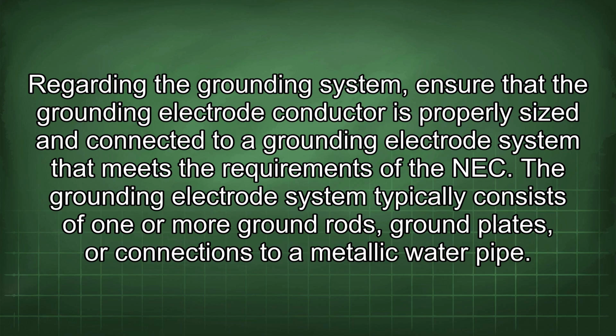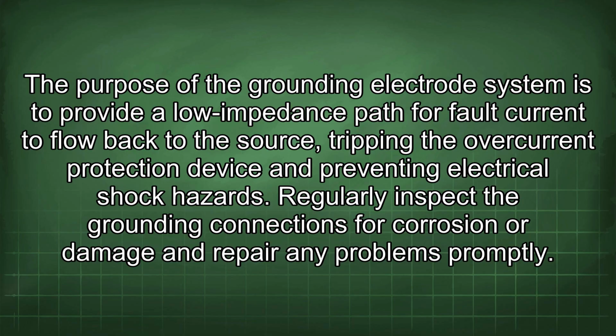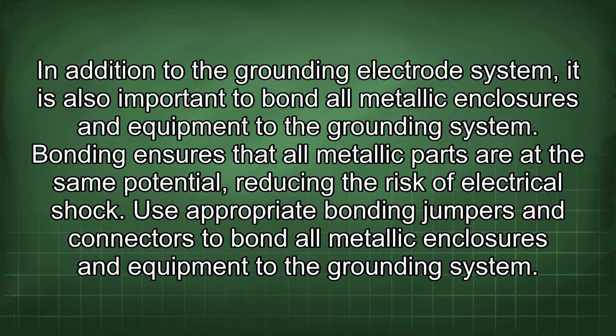The grounding electrode system typically consists of 1 or more ground rods, ground plates, or connections to a metallic water pipe. The purpose of the grounding electrode system is to provide a low impedance path for fault current to flow back to the source, tripping the overcurrent protection device and preventing electrical shock hazards. Regularly inspect the grounding connections for corrosion or damage and repair any problems promptly. In addition to the grounding electrode system, it is also important to bond all metallic enclosures and equipment to the grounding system.